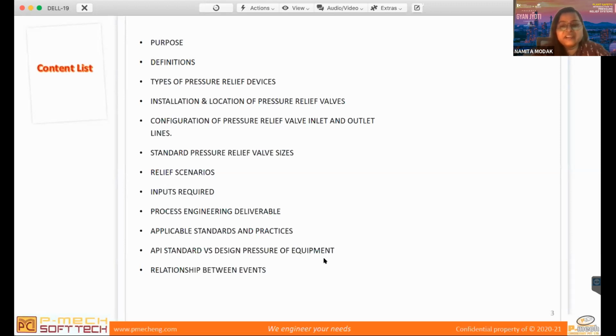And API 521 does not allow double jeopardy unless it's a common cause like total power failure or utility failure. In that case you can consider sequential or simultaneous kinds of scenarios.